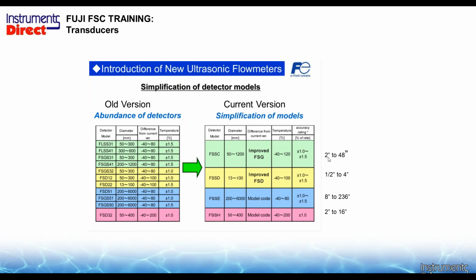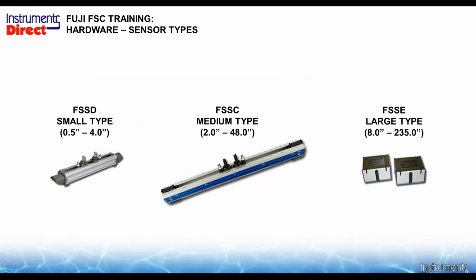Here's the workhorse there. The FSSC does from 2 to 48 inches. And here we have the small pipe sensor, 1/2 to 4 inches. And we're going to look at those next there. For those people that have some giant applications, we have another 0.5 megahertz transducer and so on. Should you not have the latest transducers, if you had an older Portaflow-C and you purchased a new transducer, we may have to update the firmware so you can see the new transducers. It's a simple task that we can do during a calibration, or we can give you instructions how to do it yourself.